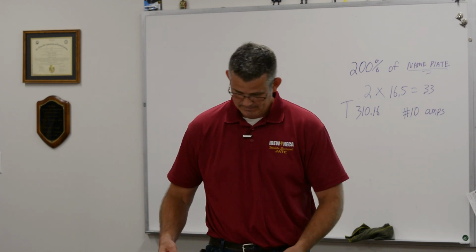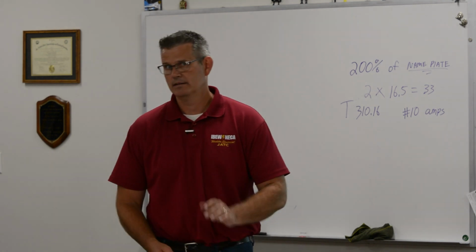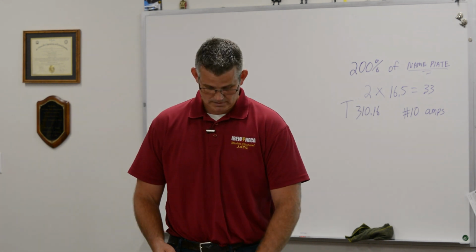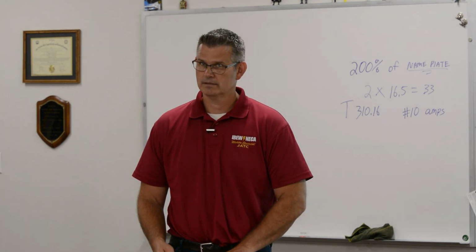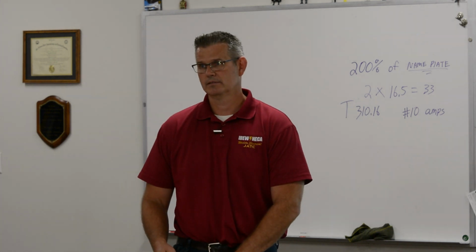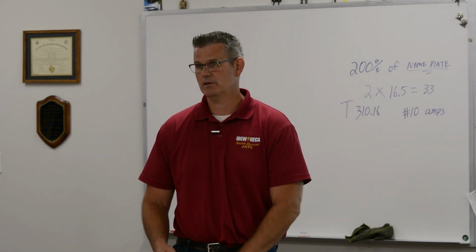No, in the 75 degree column it's 25, right? Yeah. We use it on a 20, why? Small conductor rules, right? These are referred to as the small conductor rules. Now you do have to derate the wires too. We're not covering that today, but that's the small conductor rules.